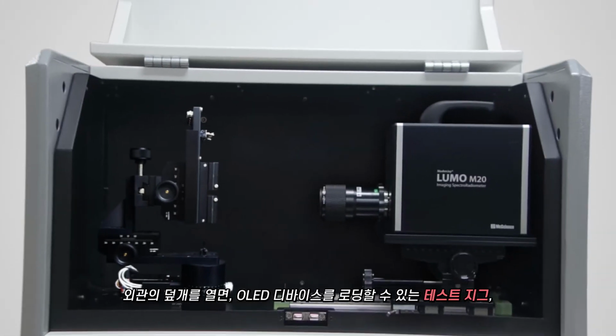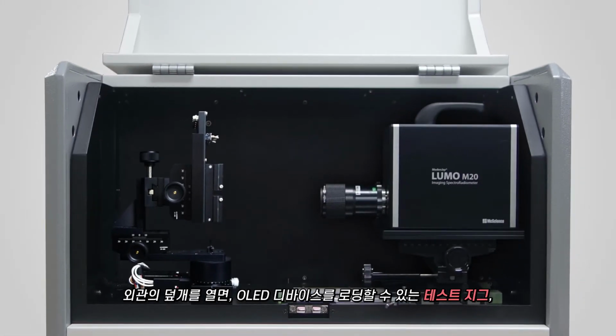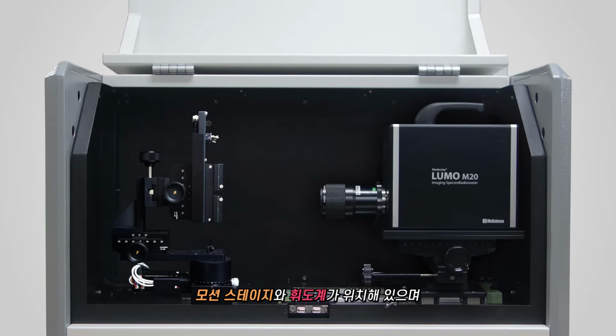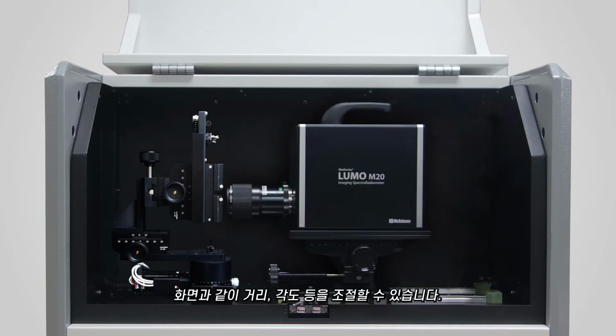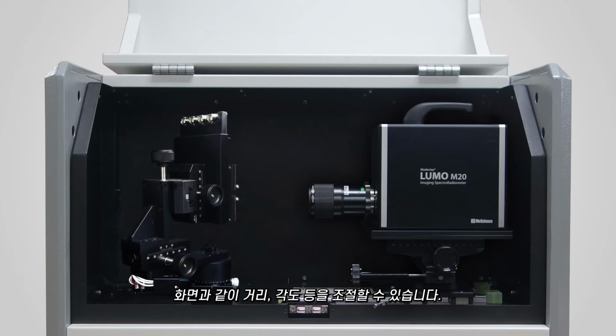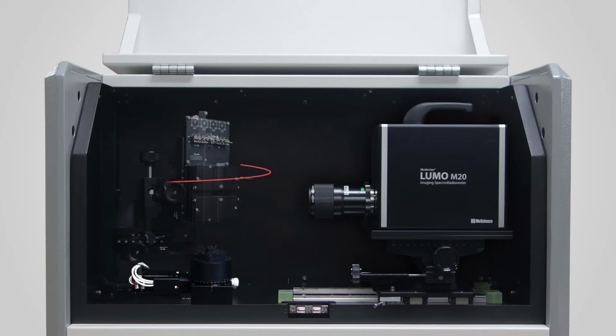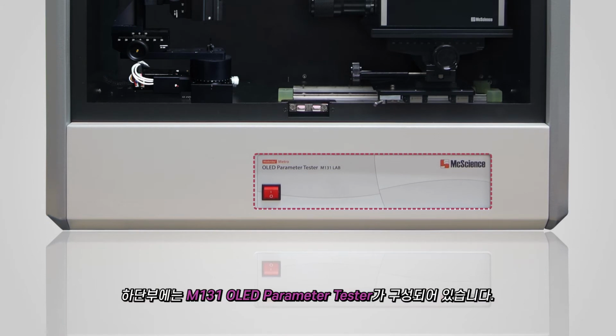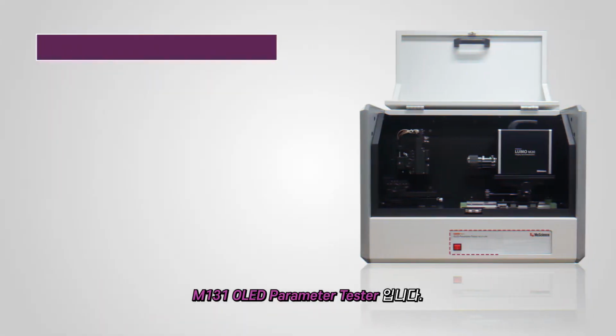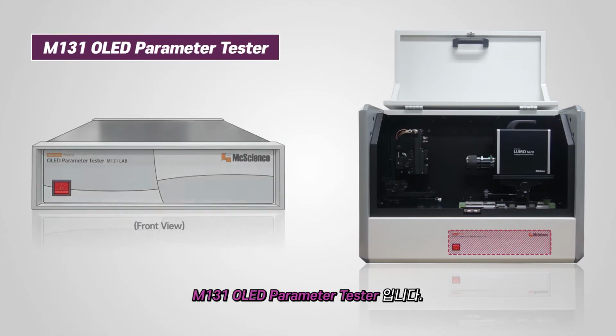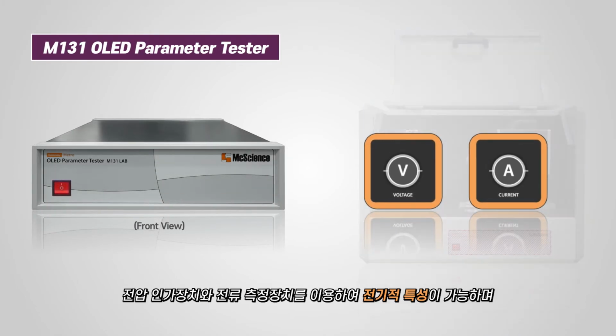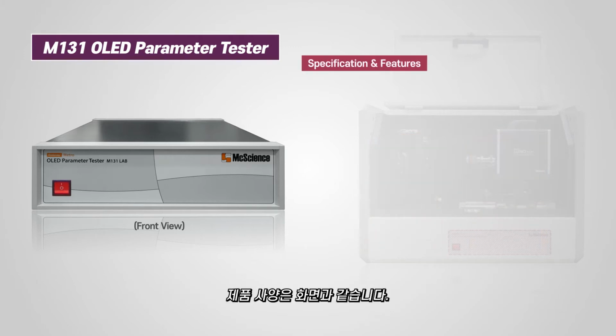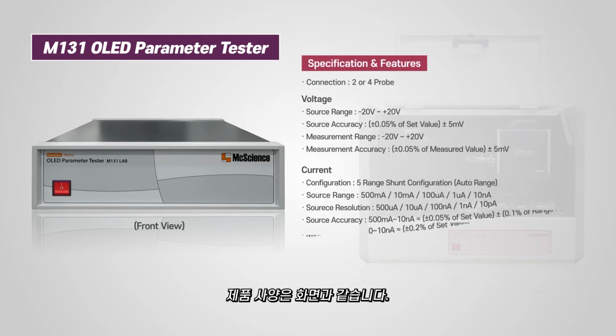Inside the outer cover is the jig where the user loads the OLED device, motion stage, and spectrometer. User can adjust distance, angle, etc., which can be seen on the screen. At the lower part sits the M131 OLED parameter tester. This is the M131 OLED parameter tester. Electrical characteristics of the device under test can be measured with voltage application and current measurement devices. The product specifications are as shown on the screen.